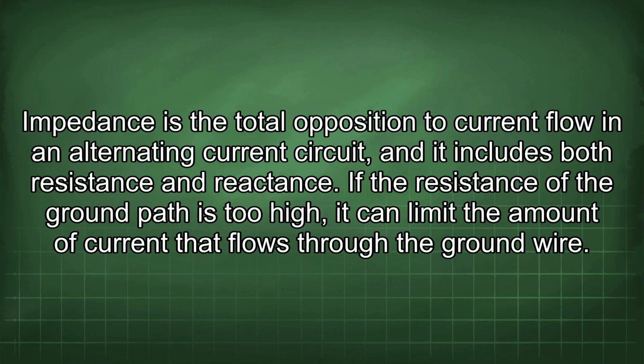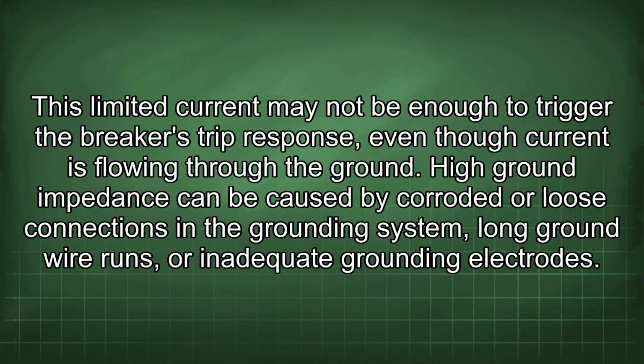Impedance is the total opposition to current flow in an alternating current circuit, and it includes both resistance and reactance. If the resistance of the ground path is too high, it can limit the amount of current that flows through the ground wire. This limited current may not be enough to trigger the breaker's trip response, even though current is flowing through the ground. High ground impedance can be caused by corroded or loose connections in the grounding system, long ground wire runs, or inadequate grounding electrodes.